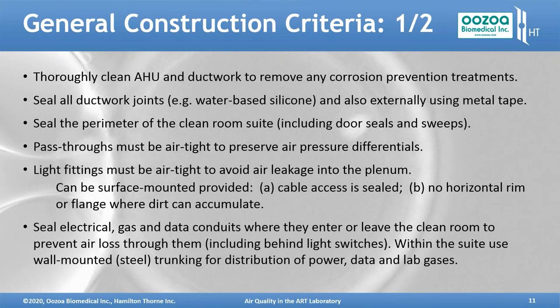Seal the perimeter of the clean room suites, including the door seals and sweeps, so that the doors aren't a source of leakage. Small leaks will typically make whistling noises, so you'll notice if they've not been found. Any pass-throughs must be airtight and have double doors to preserve air pressure differentials. Light fittings must be airtight to avoid air leakage into the plenum space.